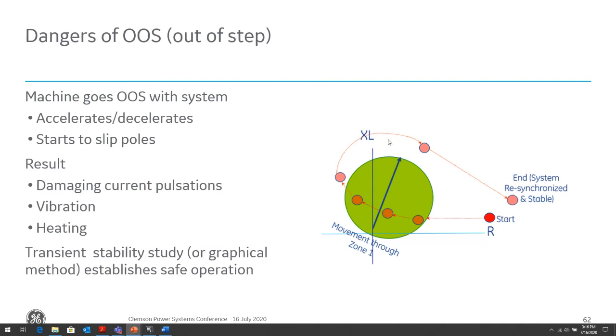So when a machine goes out of step with the system, it accelerates or decelerates depending on the type of power swing. It starts to slip poles, again, resulting in damaging vibration issues, heating issues. And this is of concern when the power swing locus, the electrical center, passes through the GSU or generator. The generator can accelerate or decelerate, changing the voltage angle between itself and the system, leading to an out of sync condition. These high levels of transient shaft torque are developed and can break the shaft over time. High stator core end flux can overheat and short the core. The GSU itself, the transformer, can be subject to high transient currents, causing overheating of the transformer.